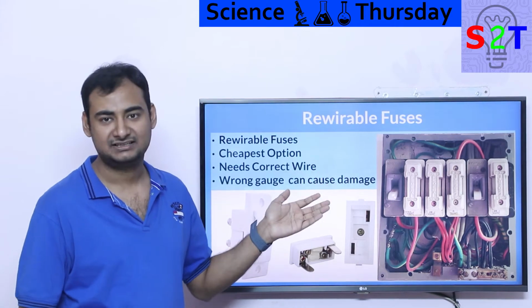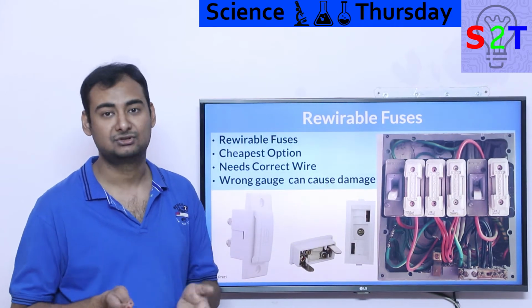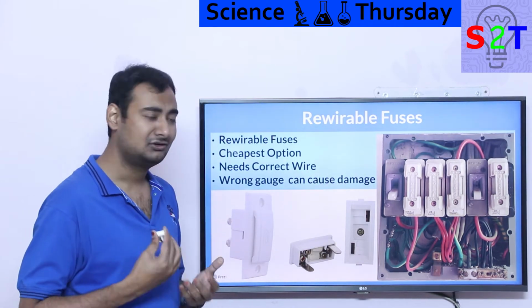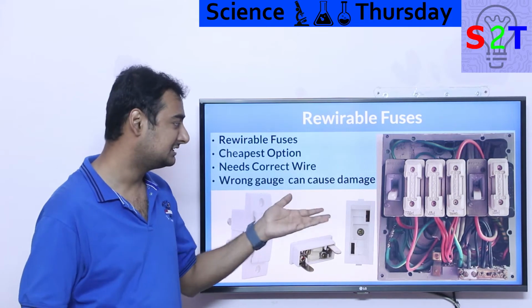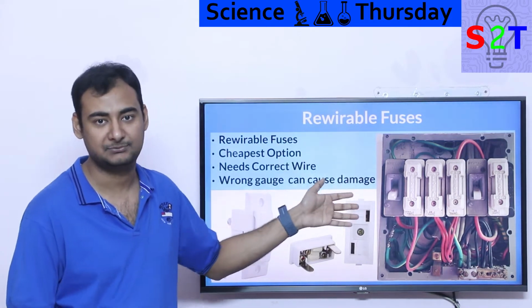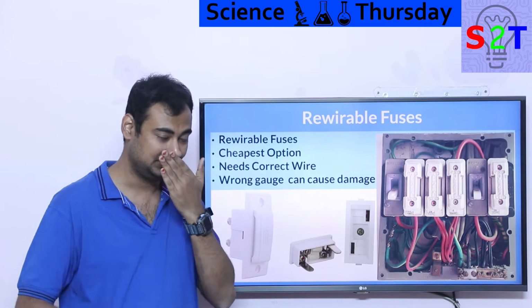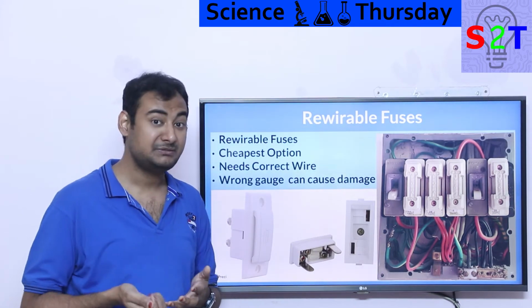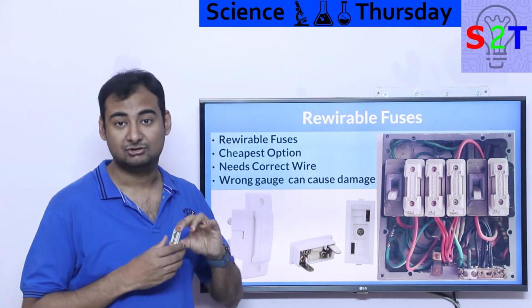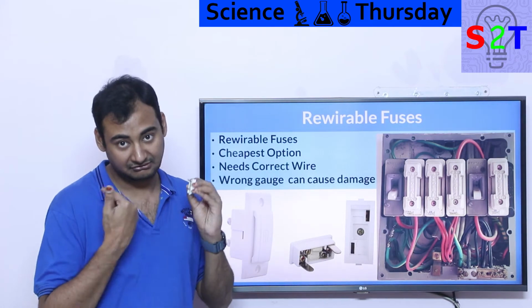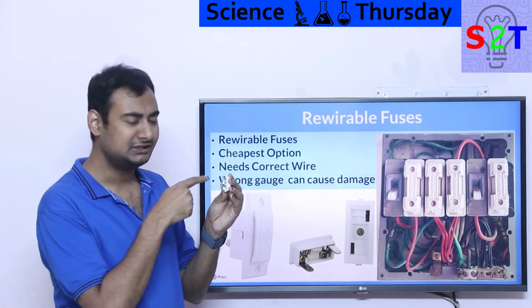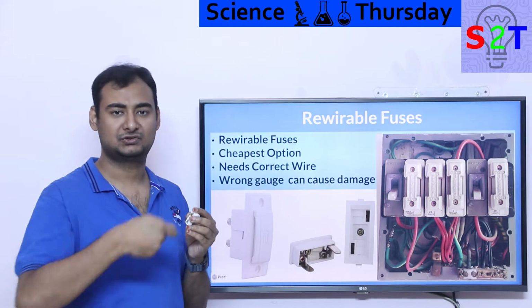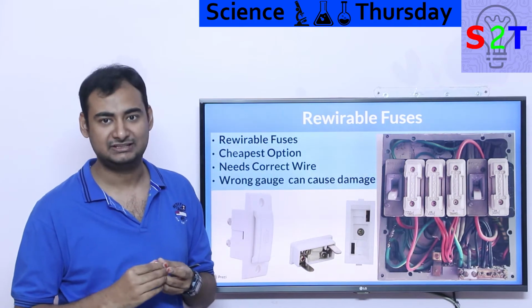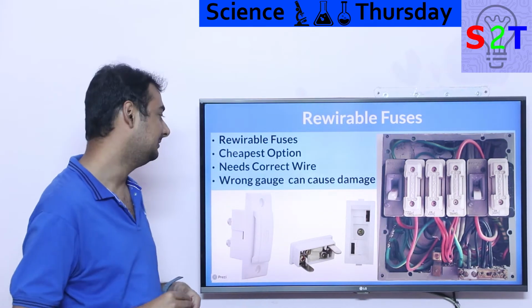The company designed that system as one size fits all, not precision made for your home equipment. You may be in a scenario where this fuse must blow at 10 amps, but 20 amp is the maximum system. So if you over corrected it, many people do that. Let's say you're doing something wrong and overloading the system, so the fuse keeps blowing up. You may be like, hey, it only has one strand of copper there, what if I put two strands? Now your fuse is no longer protecting you, simply because you crippled it by overrating it.